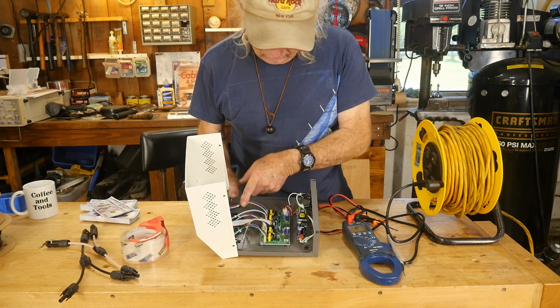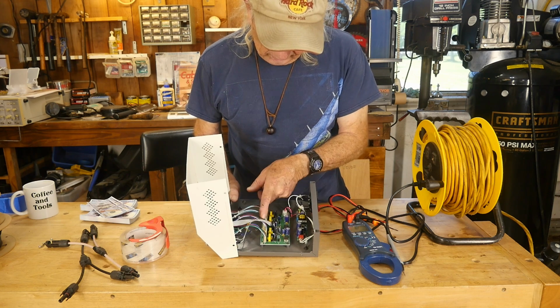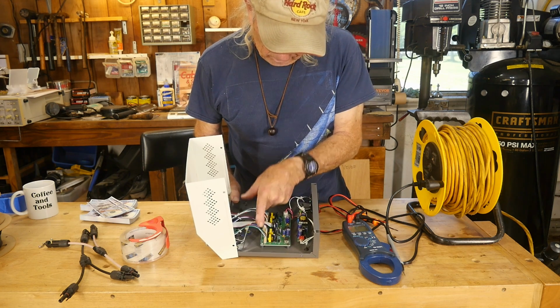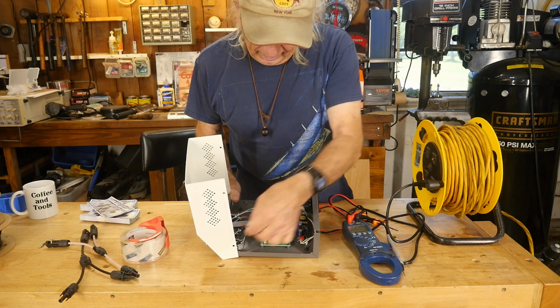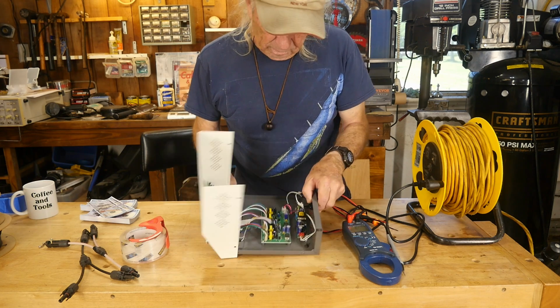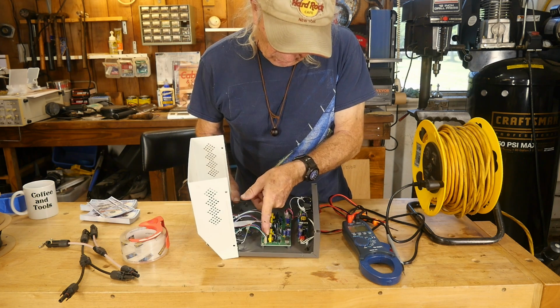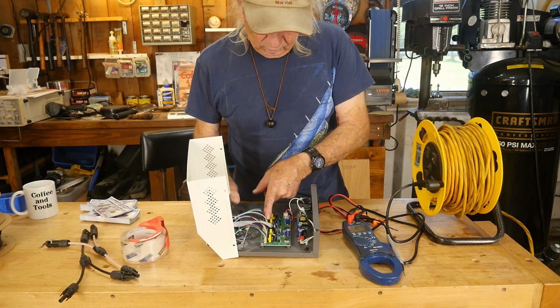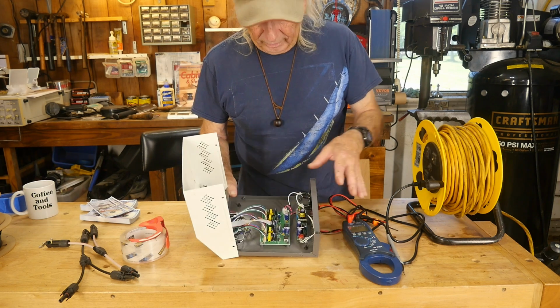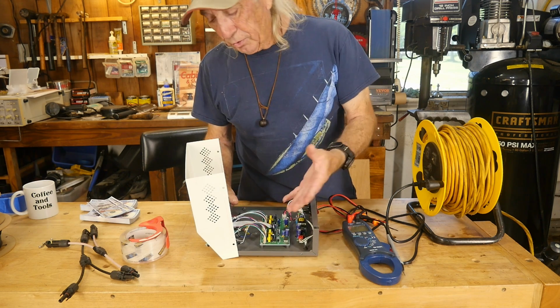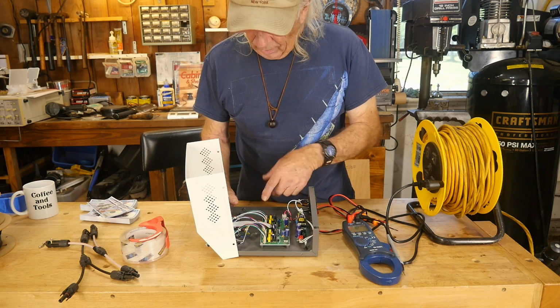Also, when I was testing these switches, I made sure that these connections were good all the way through the system, because something like that could shake loose over time, get banged around, and all of a sudden you lose the connection, and that could cause failure with the electronic board. So there are a lot of simple, straightforward things you can look for.